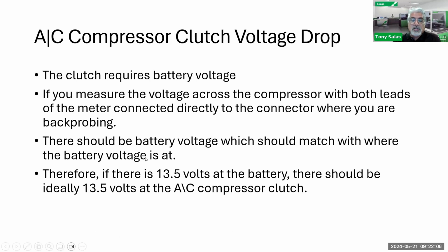So once again, you need to do a voltage drop test, but with it on and back probing the two wires. You're not going to put the positive lead on the compressor and ground it somewhere else. No, no, no, no, no. Hear me correctly: both leads must be on that compressor. You've got to put back probes, leads, jumpers, whatever you've got to do. That's the classic way to do it, and actually the only way you're supposed to do it.